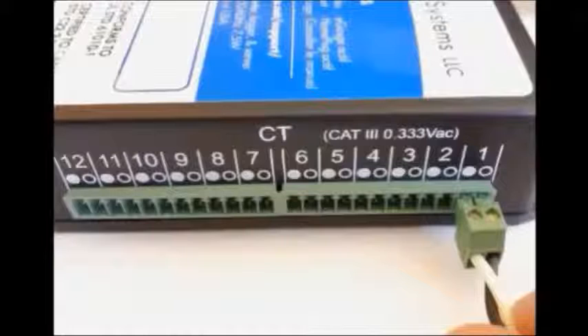The eGauge main unit has 12 CT input slots. As you can see here, the CT plug is being plugged into CT slot 1. Please see the CT selection guide for more information. The installer should fill out the installation sheet as the CTs are installed, noting the identity name of the load, the CT amperage, and which phase the CT is connected to, phase A, phase B, or phase C.